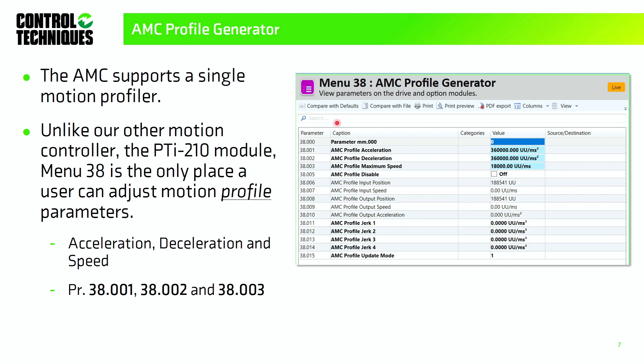Menu 38 is a single motion profiler. Some of you may be familiar with our older motion controller, the Epsilon drive, and Power Tools software, which allowed you to set up motion profiles individually — each with its own accel, decel, and speed. That's not the case with the AMC. The takeaway is: if I'm doing positioning and I want to update the accel, decel, or speed, I need to update menu 38 first.